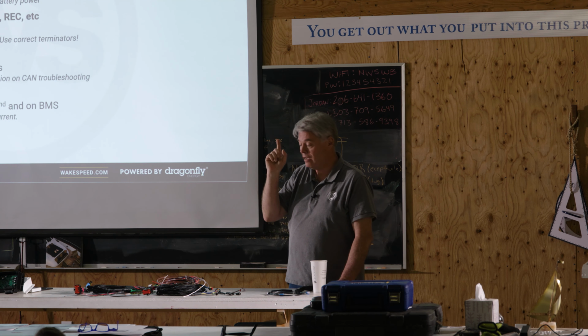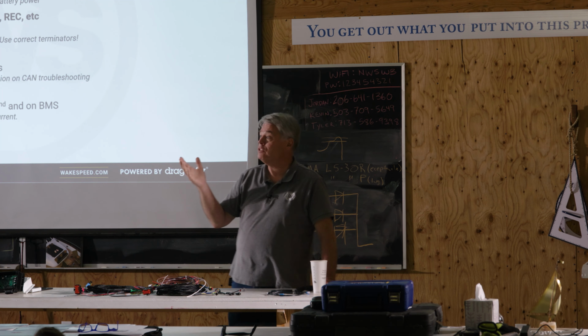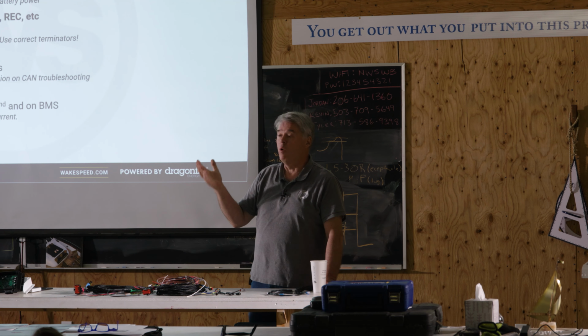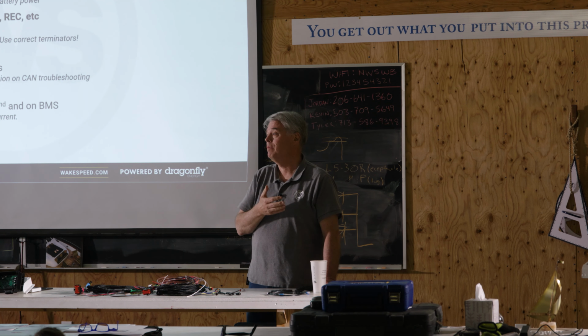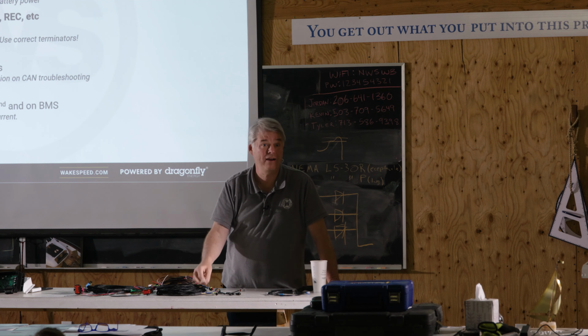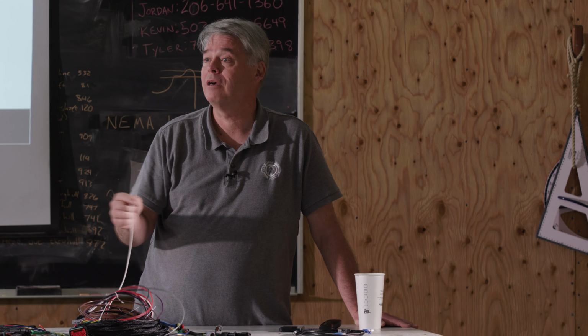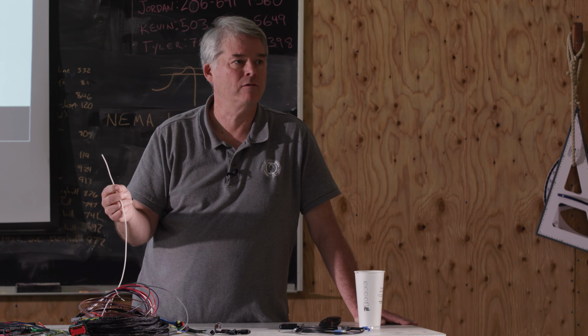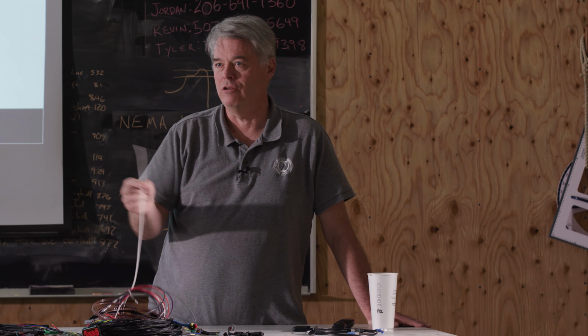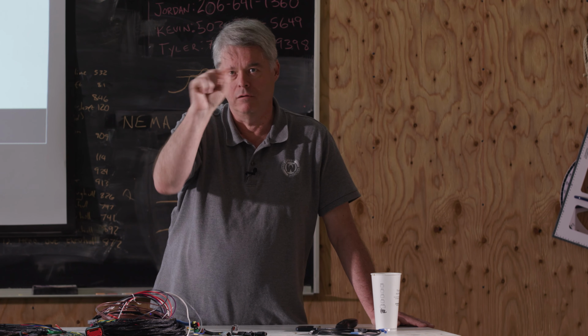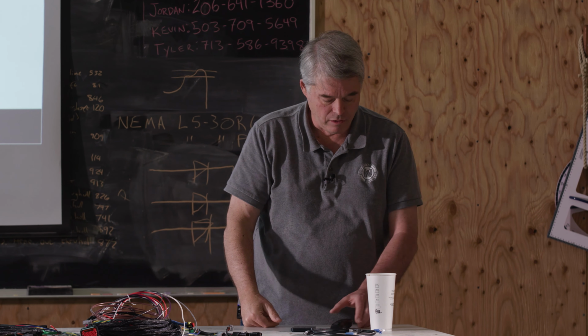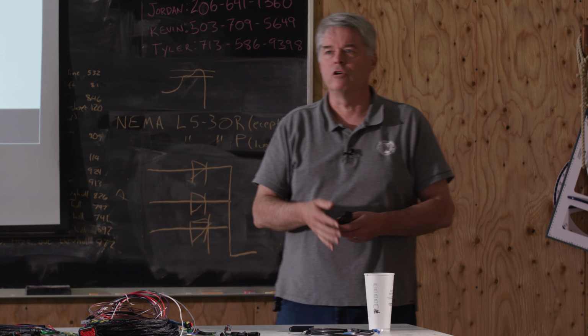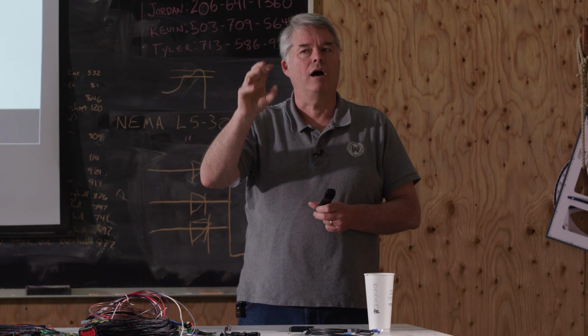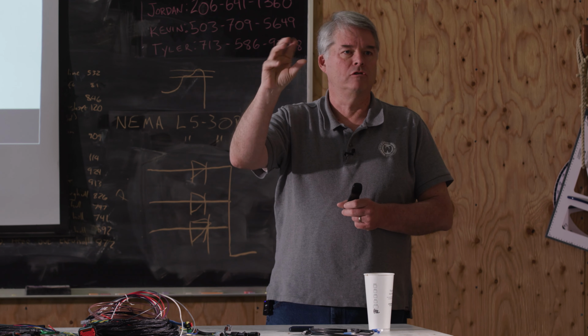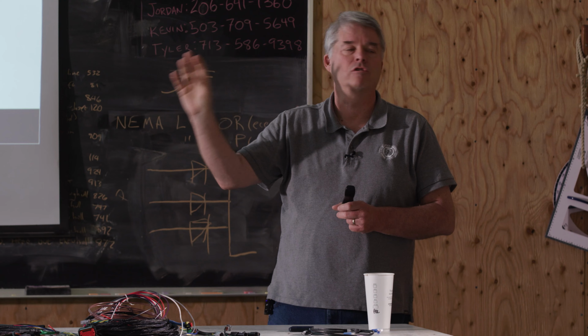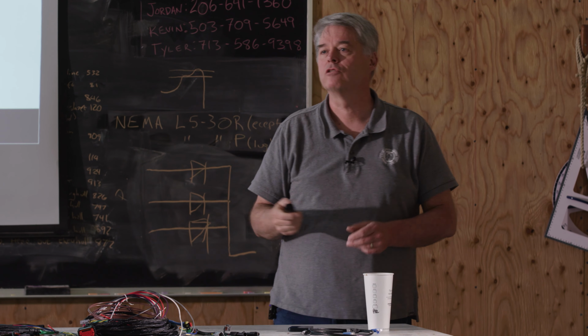What happens is the regulator won't go anywhere without that wire being enabled - it's held in standby mode. A very quick test is to temporarily connect this white wire to positive battery voltage. If things start working, then you know this is the issue, and it's usually the little jumpers on the Victron. You also need to know that on the Victron Lynx, you have to go in and declare that you're talking to an alternator - there are auxiliary circuits you have to declare are being used with an alternator. That's part of the setup of the Lynx, so make sure you do that.